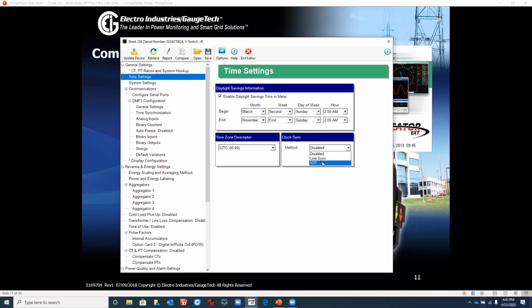Or you could choose a line sync, which uses the 60 hertz frequency to sync. Before I get into the problem with the line sync choice, you have the option of 50 hertz, which is used in different parts of the world, South America to Europe, where you can change different frequencies. But the line sync allows you to sync to that frequency while the meter is online. If the meter is powered up from the phases and you actually lose power in an outage, the meter will switch automatically to its internal clock. So either way, the meter continues to maintain the time.